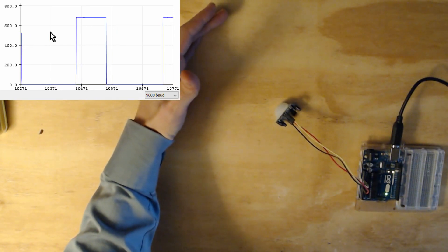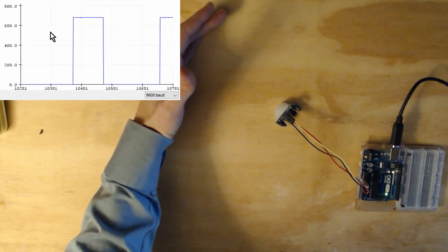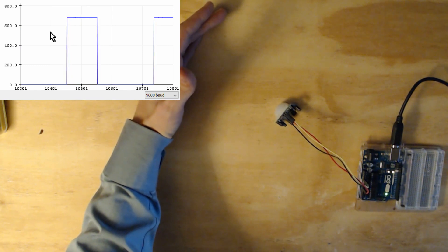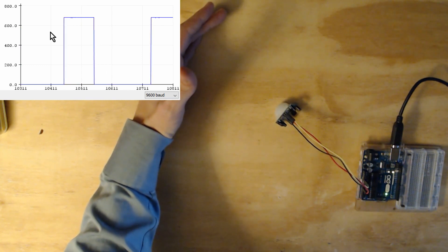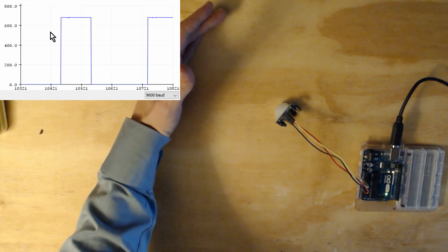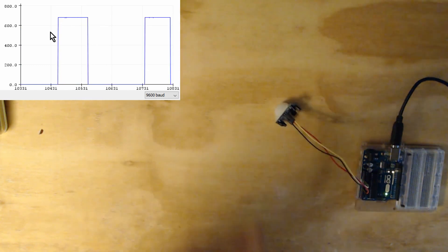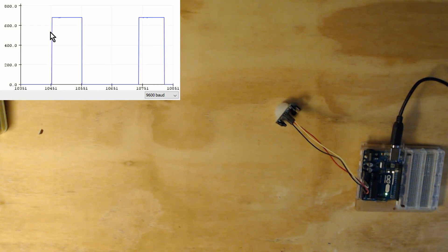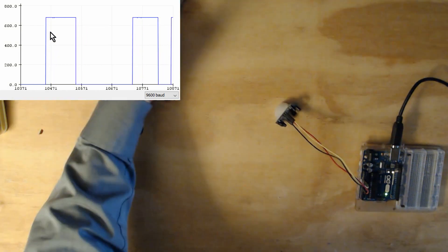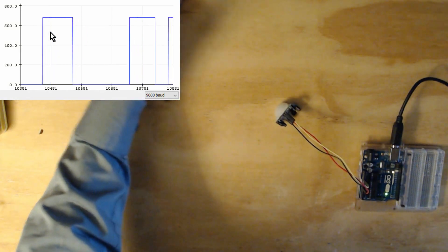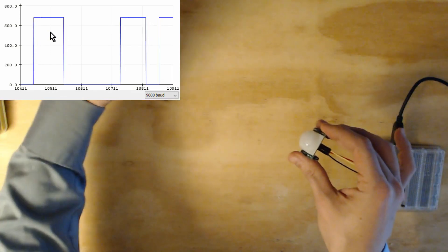So this is a digital output. I have it hooked up to analog so that I can see any swings or anything else, but the time delay is how long it will take before it stops sending the signal. So as long as there is movement, then the signal will remain.